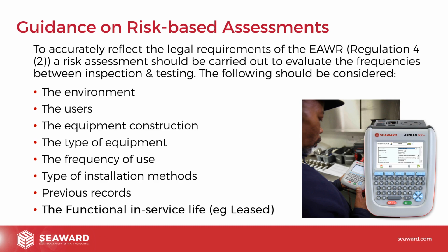So the guidance on risk-based assessments, to accurately reflect the legal requirements of the Electricity at Work Regulations, Regulation 4, Paragraph 2, is that a risk assessment should be carried out to evaluate the frequencies between inspection and testing. So in the Code of Practice, they've always had 7 things that we've considered, and under the 4th edition we always went through these 7 things. The environment it's being used in, who's going to use it, the actual construction of the equipment, is it class 1, class 2, the type of equipment, is it maybe handheld equipment, stationary equipment, the frequency of use, how often we're going to use it, the type of installation method, so is it in conduit, trunking, is it a cable run across the floor, and also our previous records.